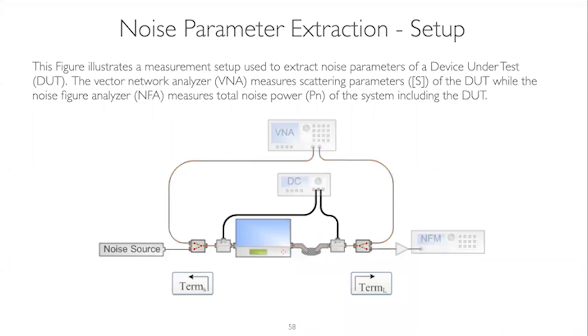Once you're done measuring the S-parameters and the tuner impedance points, you turn on the noise path, and that's where you start tuning the impedance and measure the noise figure on your noise figure meter. Here we're just showing an external noise figure meter, but in most cases we use, for example, a PNA-X that has the noise figure meter built directly into the VNA.